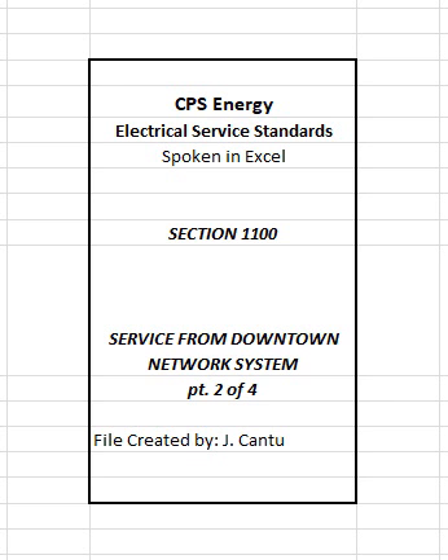B. Easements. Customer shall grant or provide CPS Energy with necessary easements for transformer vaults or rooms and associated electric lines and equipment. Customer shall coordinate with the CPS Energy customer service representative for specific details and for conditions of use of such easements. C. Accessibility. The design of a transformer vault or room shall ensure full 24-hour immediate access and allow close approach, be within 8 feet of a hard driving surface.